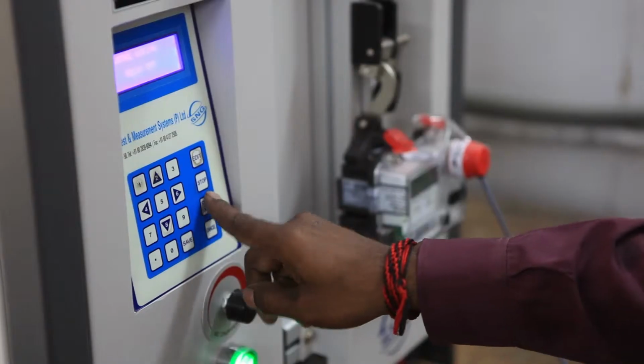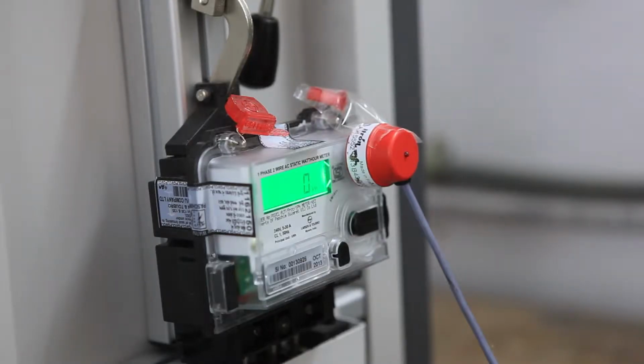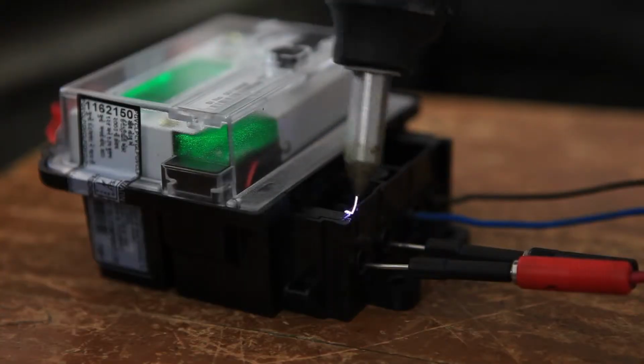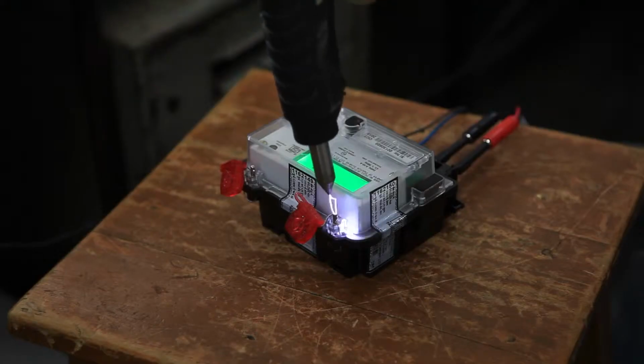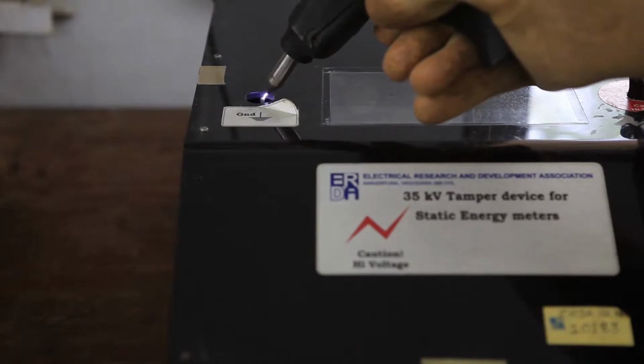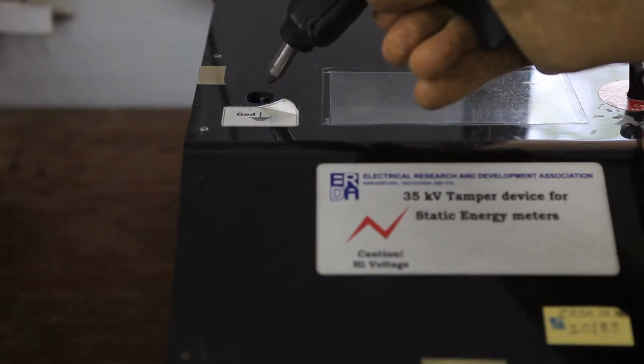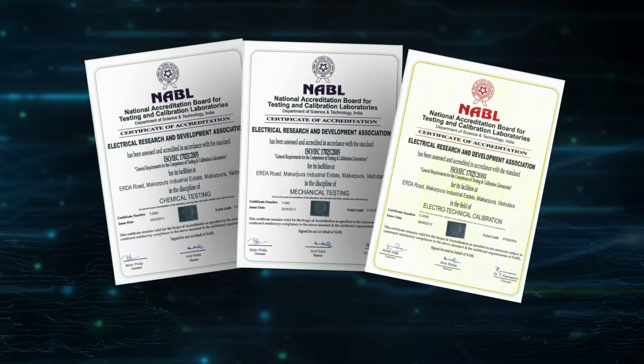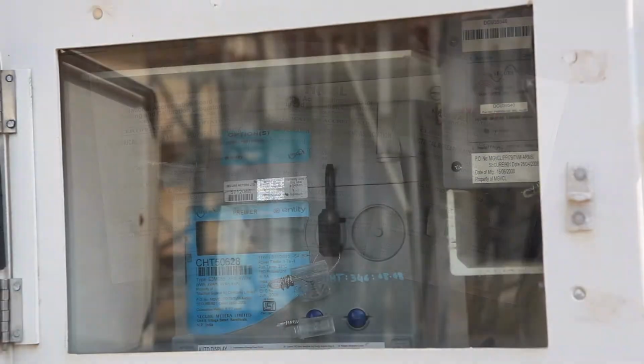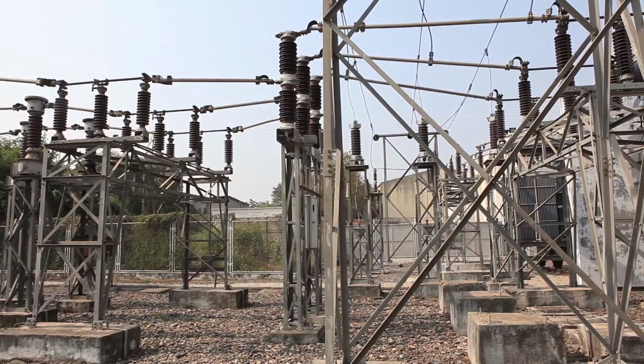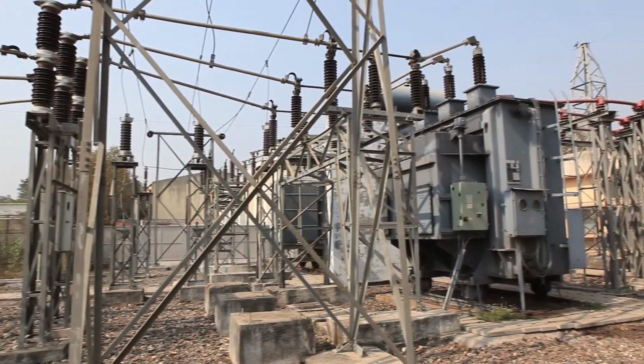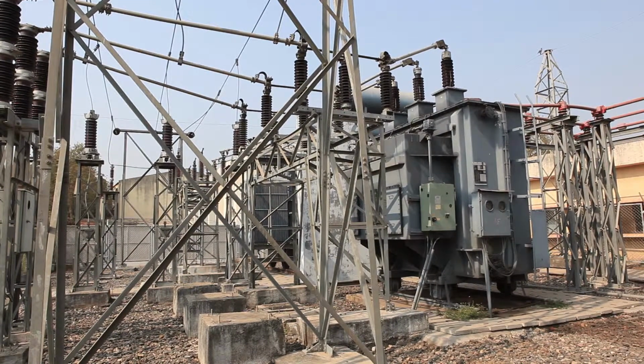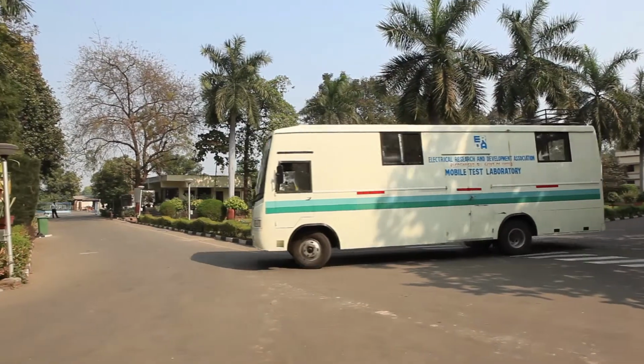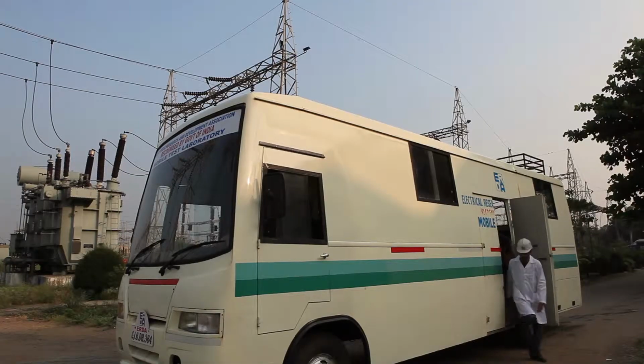26 types of tamper conditions are simulated in this laboratory. The special tamper test of applying high frequency high voltage spark of 35 kV has been developed by ERDA. We offer NABL accredited services for acceptance and routine testing as well as calibration of energy meters at the utility's premises. ERDA mobilizes several teams for site testing.